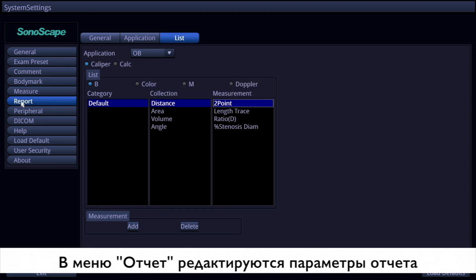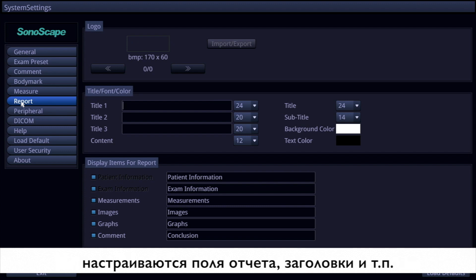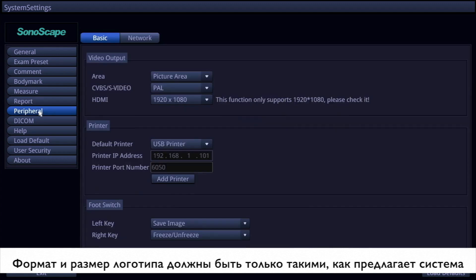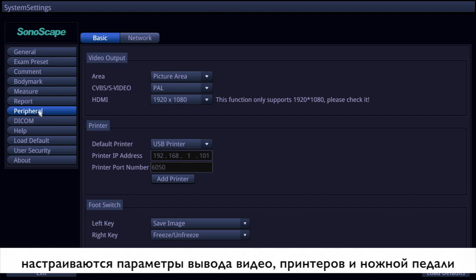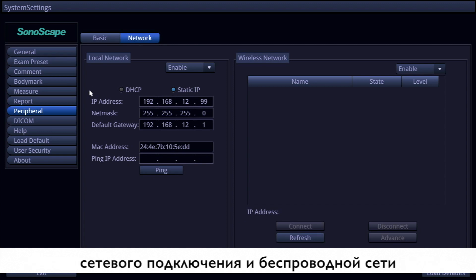Under the report item, the elements on the report are adjustable. Hospital logo importing is available, but the format and resolution must strictly follow the instructions. All adjustments on this page will be shown directly on the report. There are two pages in the peripheral item: the basic page for video output, printer, and foot switch settings; and the network page for internet connection.